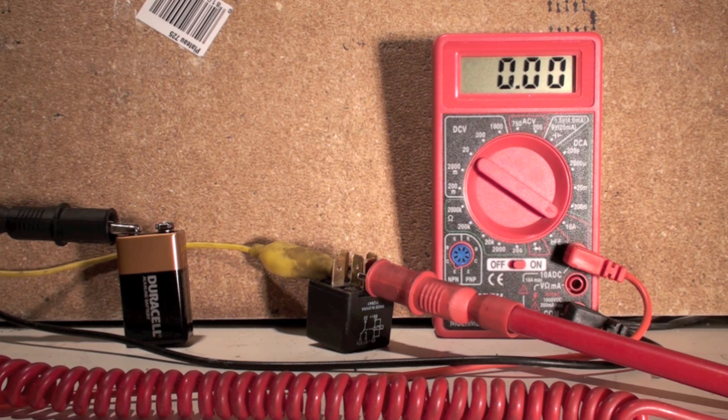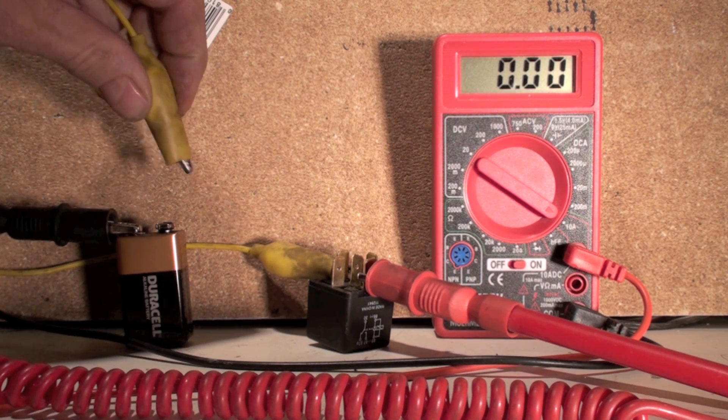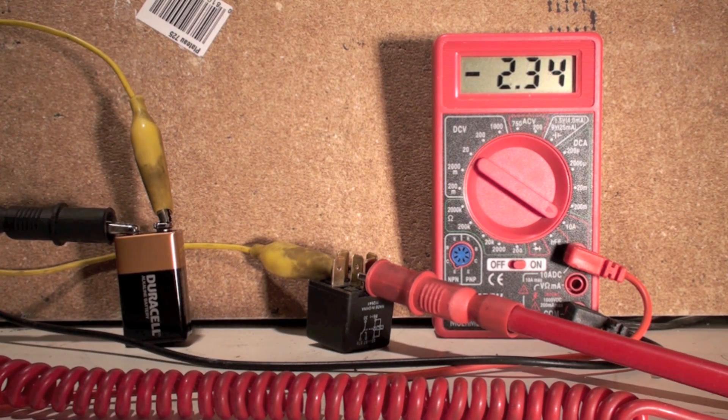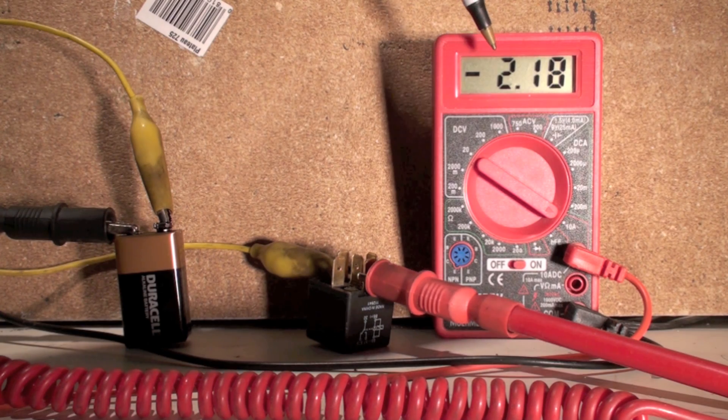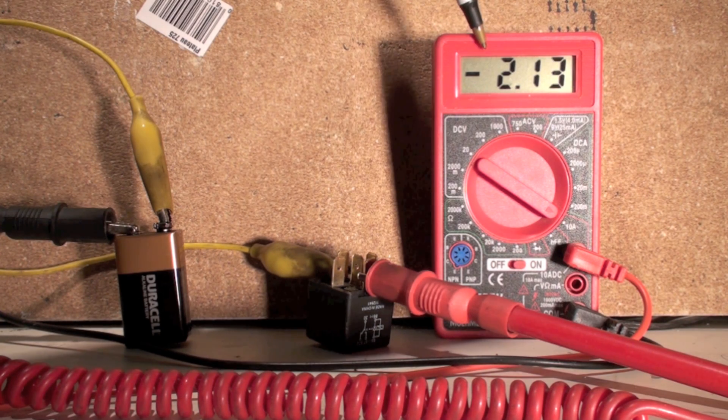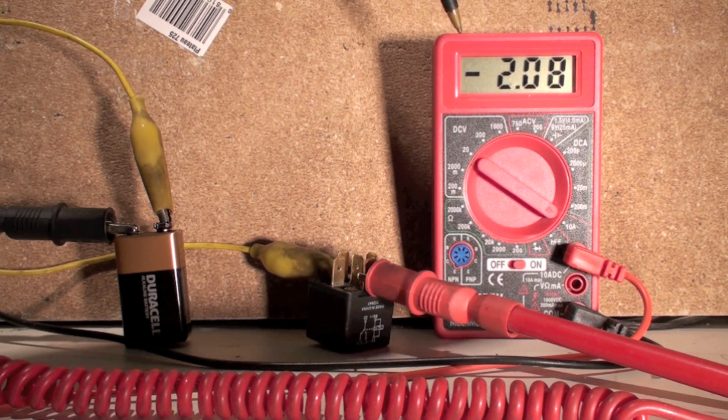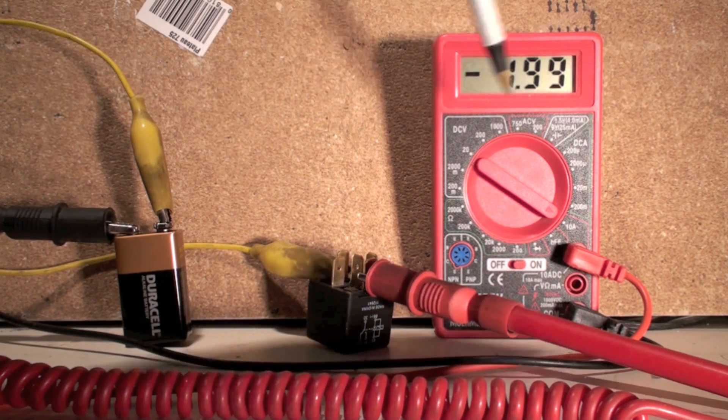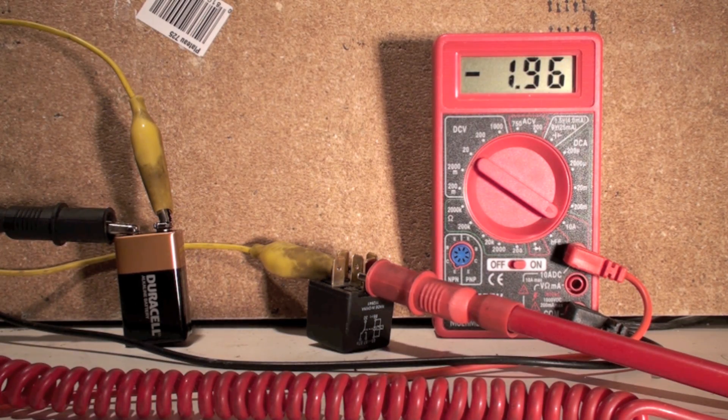I'm putting this in line, so when I put this jumper on here, you can see I'm reading an amp draw. Now it's minus because I got it hooked up backwards, but it will read the amp draw. It has to go through the meter.